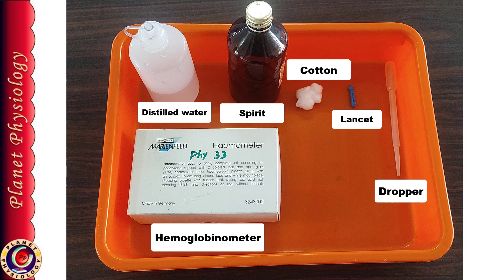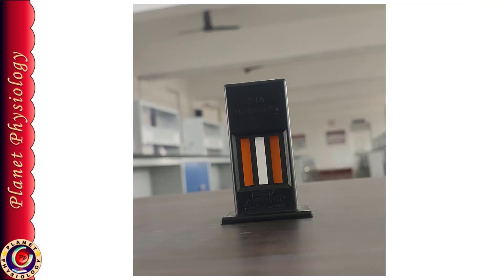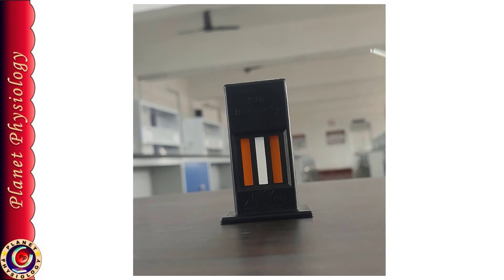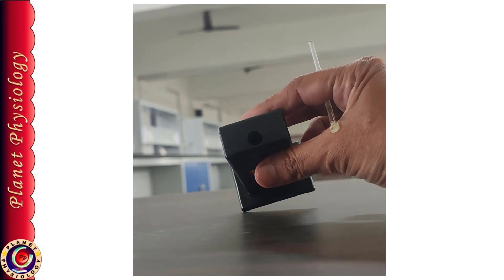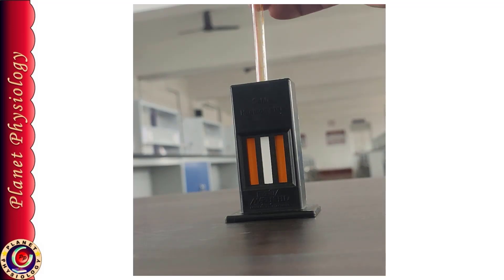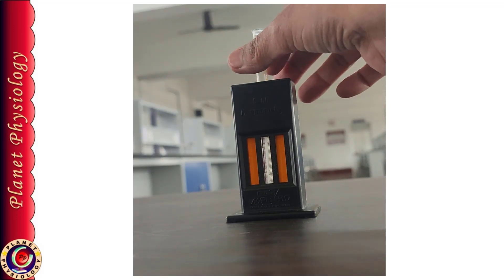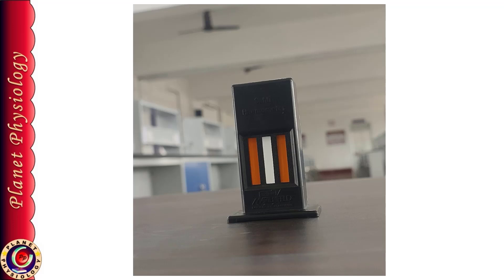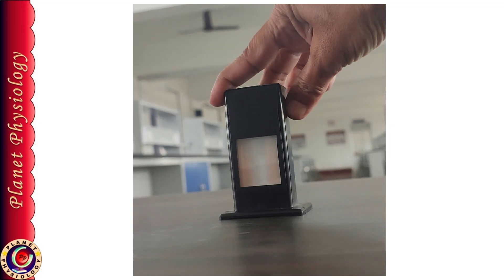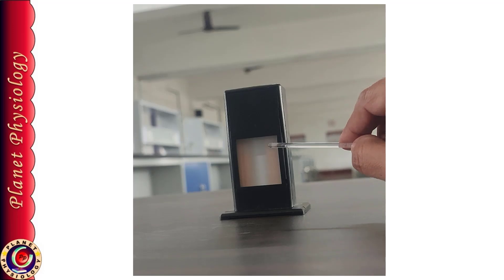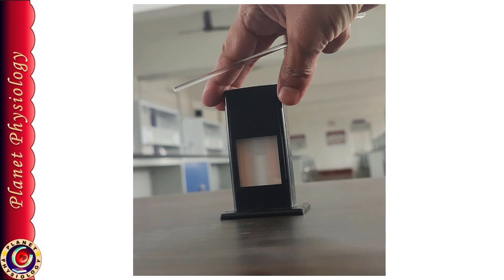Each of these components plays a crucial role in the accuracy and efficiency of the test, and hence it is essential to know them thoroughly. Sahli's hemoglobinometer is a specialized device used to compare the color intensity of acid hematin with the standard color. These are the standard comparator plates. Between these two plates, there is space to accommodate the hemoglobin tube. The back side of this comparator has an opaque white plate, which helps to match the color of acid hematin in the tube with the standard plates while holding it against the light.